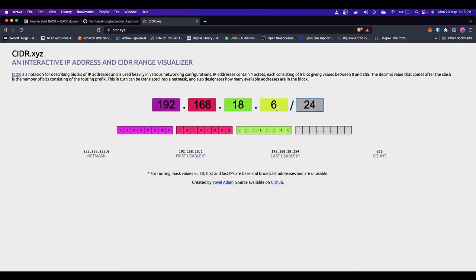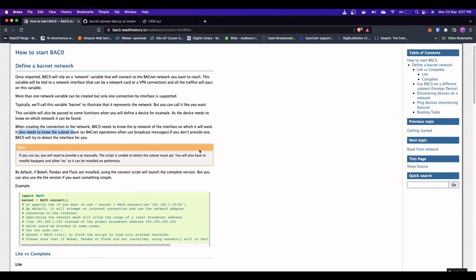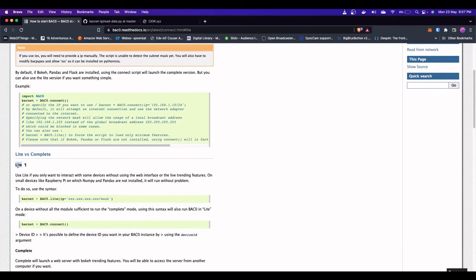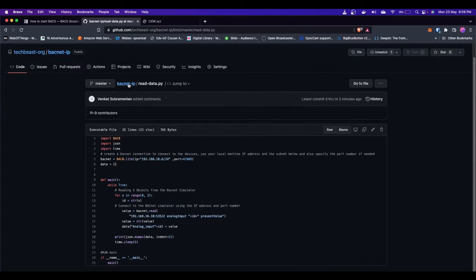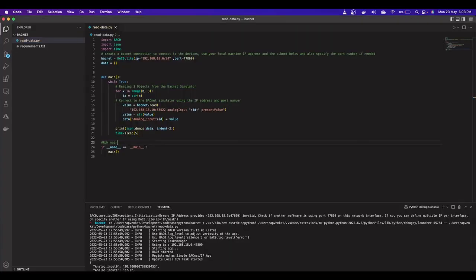My client machine IP is 192.168.18.6 — that's the machine I'll use to connect to the BACnet simulator running on 192.168.18.10. BAC0 needs this subnet to connect and read data. We'll use BAC0 Lite since we don't need a web interface: just set bacnet = BAC0.lite() with your IP address, port, and subnet mask. The full code is on techbeast-org's GitHub page under 'bacnet-ip.' Run 'pip install -r requirements.txt' then execute read_data.py.